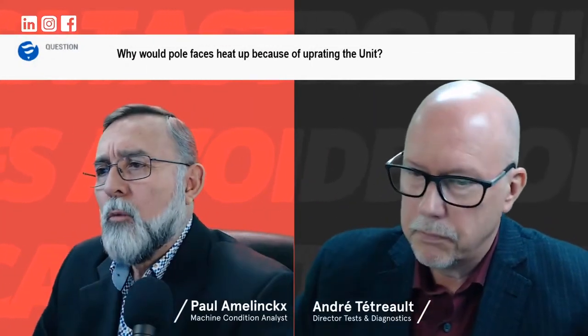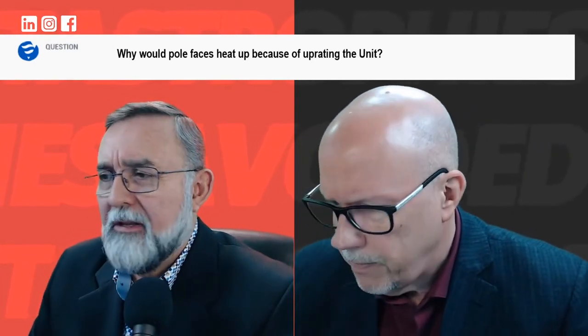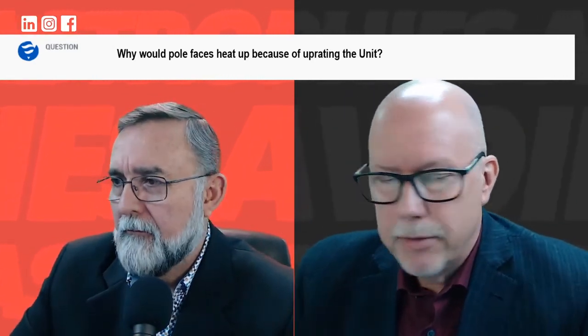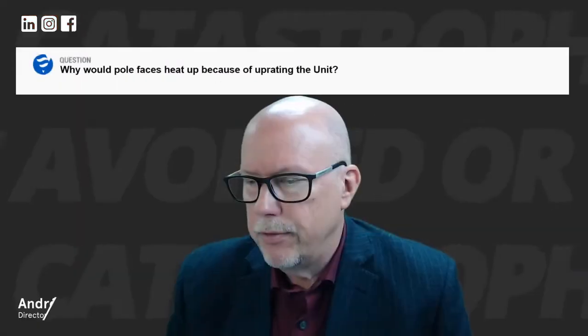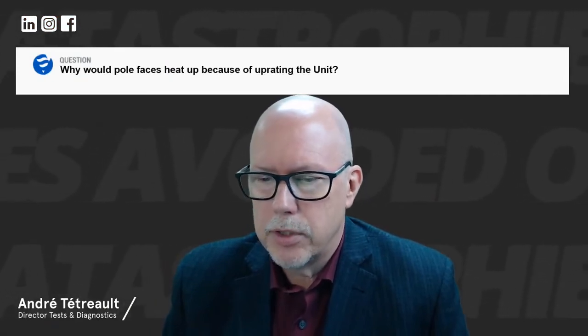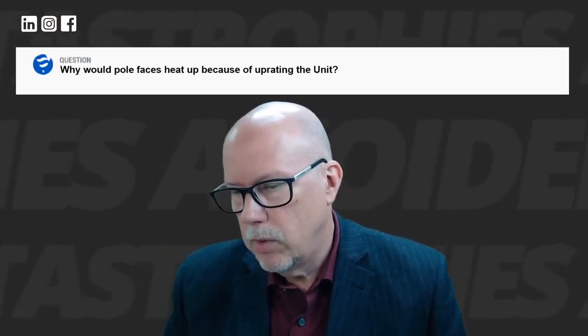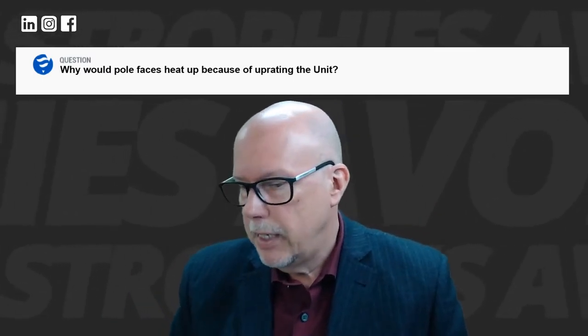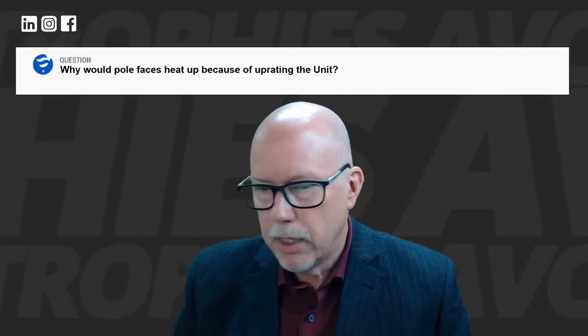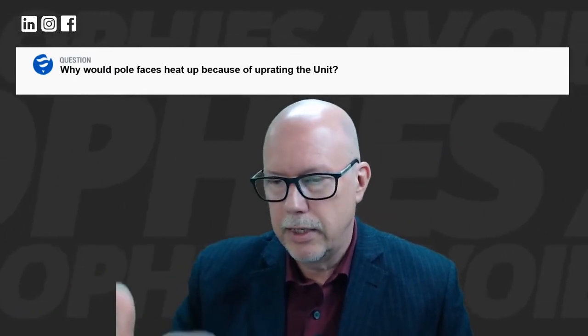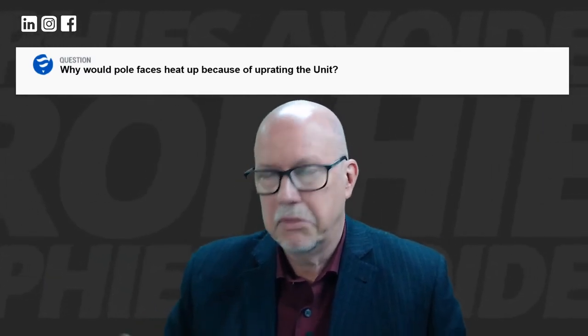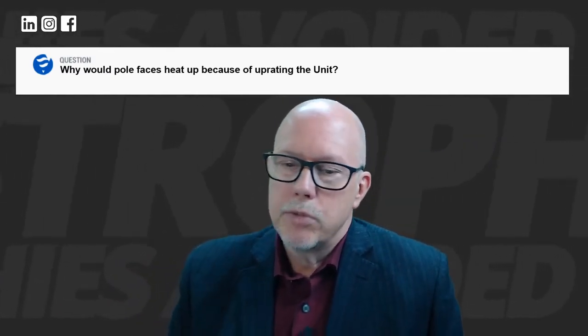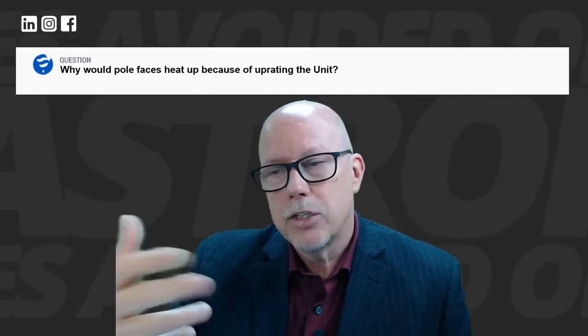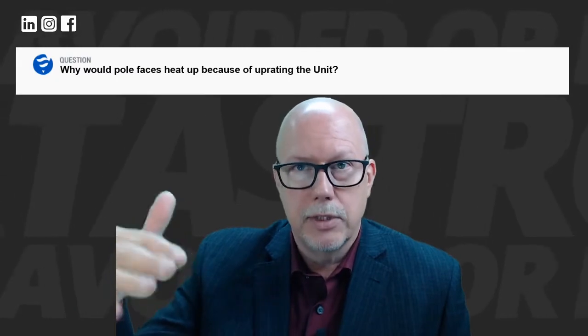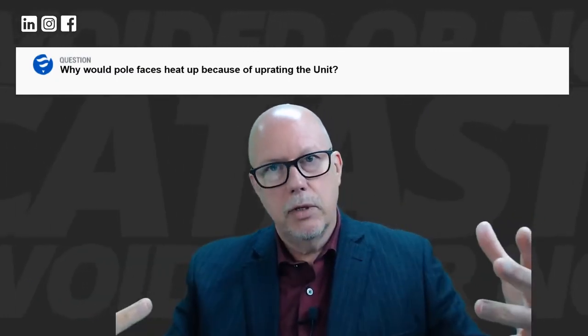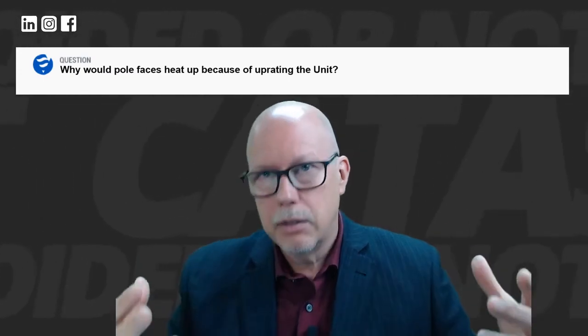There's another question here: why would the pole faces heat up because of uprating the unit? Well, the reason is that if you increase the turbine output, in many places the water is already producing the maximum amount of megawatts based on the turbine design. So in many cases they can't put in more units, but turbine technology has improved. In some cases they can put a new turbine in and get an extra 3, 4, 5% output, which means you'll increase the electromagnetic stress between the rotor and stator by 5, 6, or 7%. That extra power will have a tendency to heat the components.